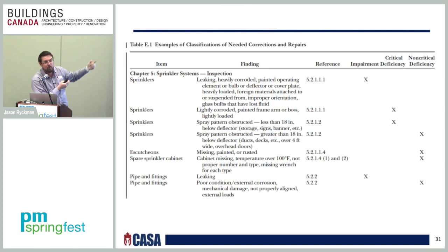Is there paint on the operating element, which is the glass bulb or solder element? Or is the deflector or cover plate heavily loaded? Foreign materials attached to or suspended from it, or improper orientation, because each sprinkler has an orientation specification. It's either upright, pendant, which is down, or sidewall, which is on the side of the wall. The orientation has to be correct.